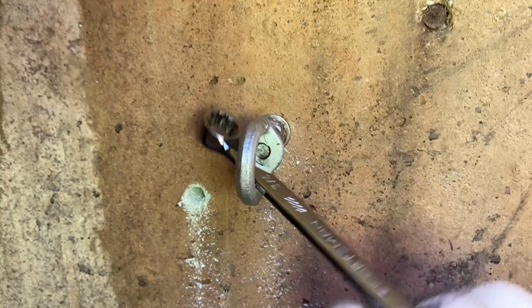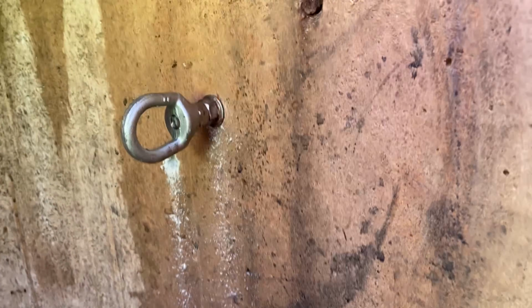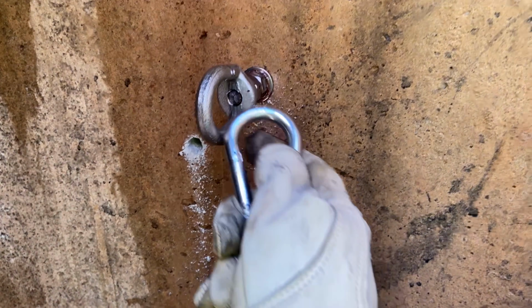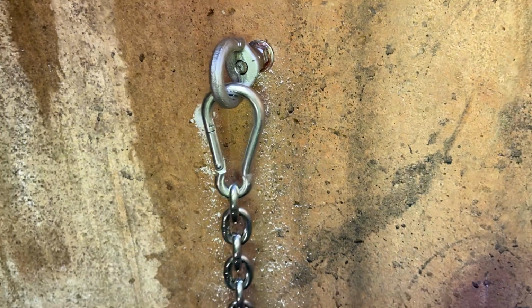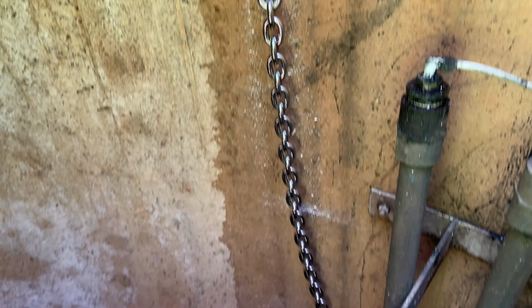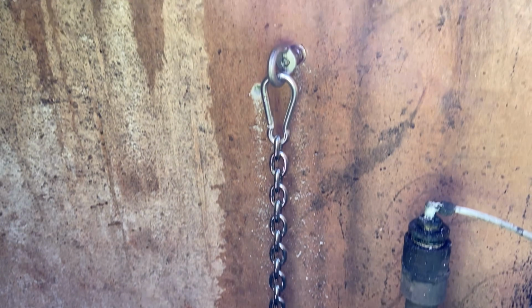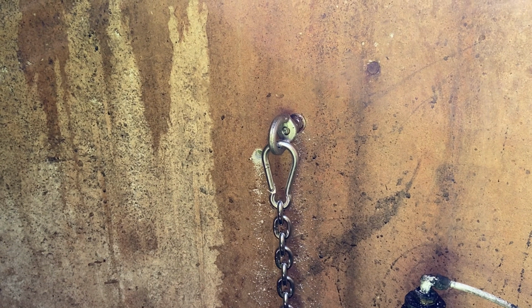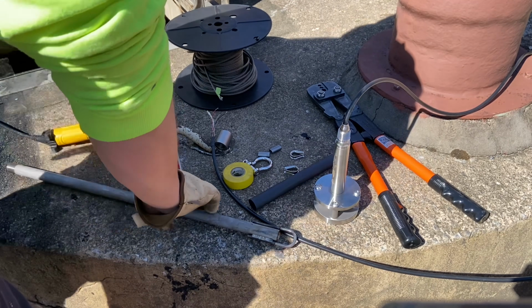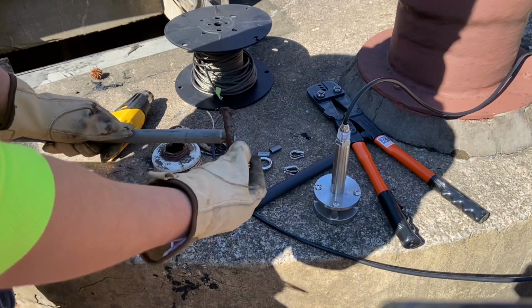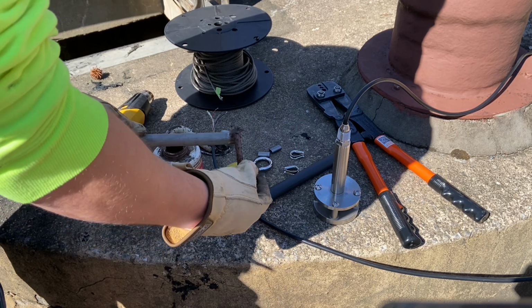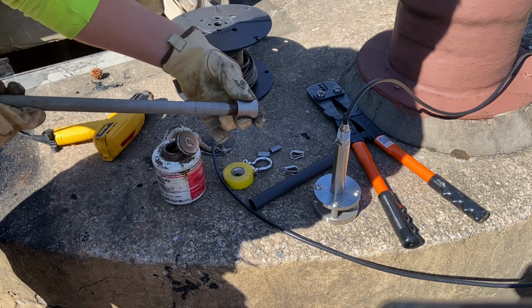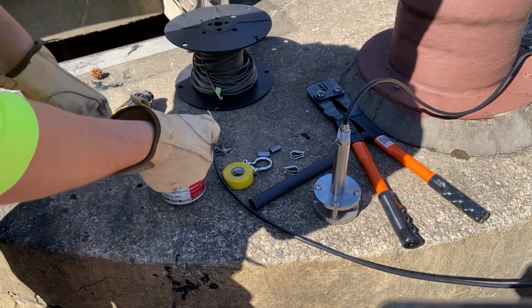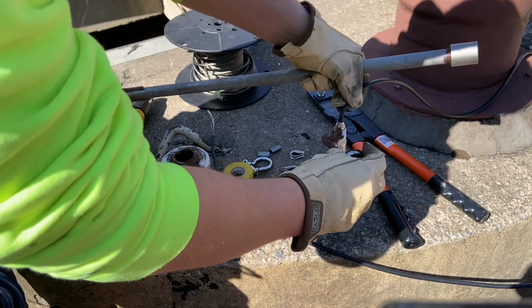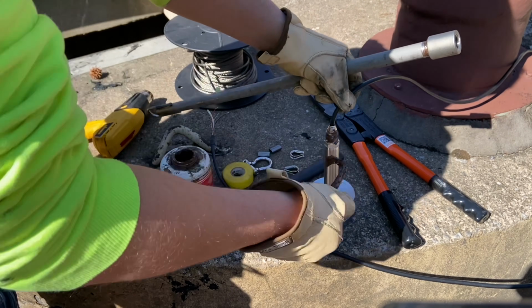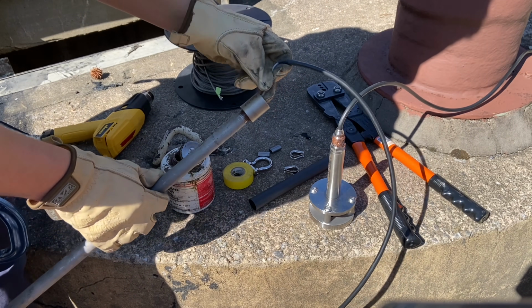So the way you're going to see me hang this transducer is a way I came up with a few years back, and we've had pretty good luck with it. And the people I'm doing this for have also had pretty good luck with it, so we always do it the same way when we're working here. In this installation, the transducer is just going to hang freely in the well. So the electrical cable on the transducer, the black cable, is actually rated for about 200 pounds, but we always add a stainless steel cable to get our weight rating to up around 500 pounds, which is a lot of rags, but we can definitely achieve that, trust me.